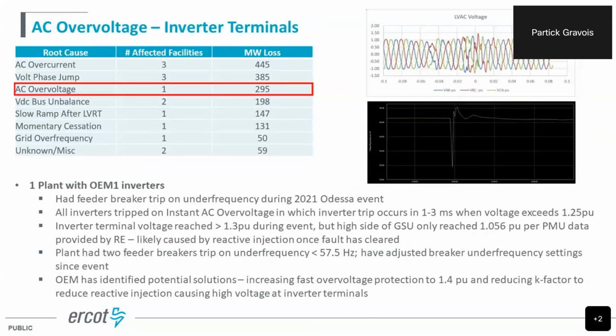AC overvoltage, seeing this one again, kind of typical. This facility, this is the one that had its feeder breakers trip on under frequency last year. They disabled that, and now they were tripping on overvoltage. So we're seeing this, you know, they're fixing the original thing from 2021, but now they're having a different thing trip them off in 2022. This is, again, we saw voltage at the POI only get to 1.06, but we had terminal voltage reaching above 1.3 per unit. They still had a couple of feeder breakers trip on the below 57.5 during this event as well.